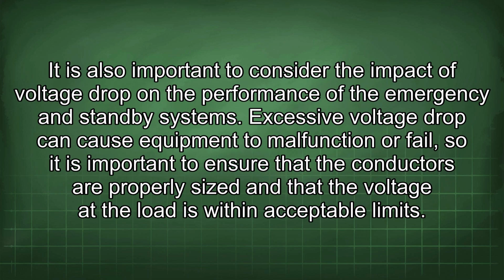It is also important to consider the impact of voltage drop on the performance of the emergency and standby systems. Excessive voltage drop can cause equipment to malfunction or fail, so it is important to ensure that the conductors are properly sized and that the voltage at the load is within acceptable limits.